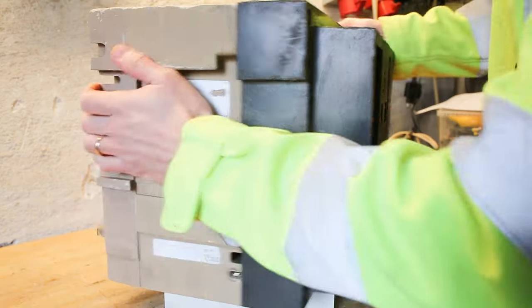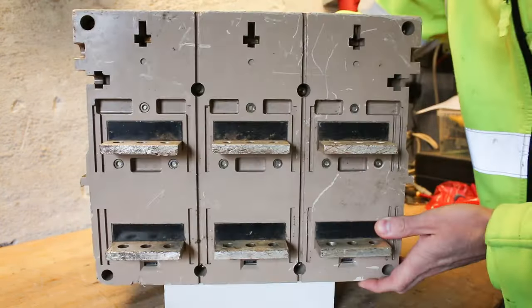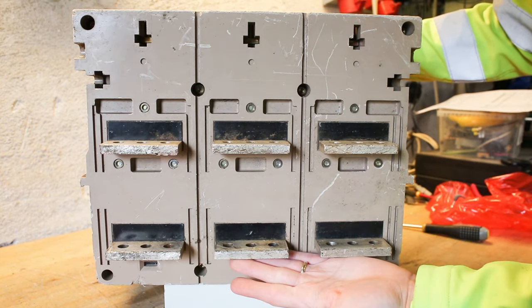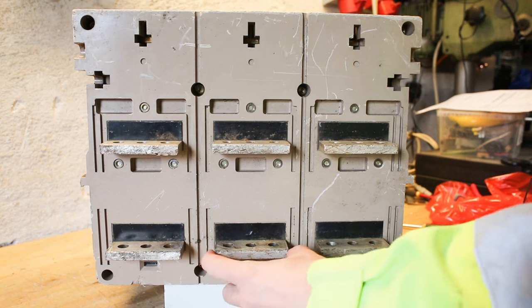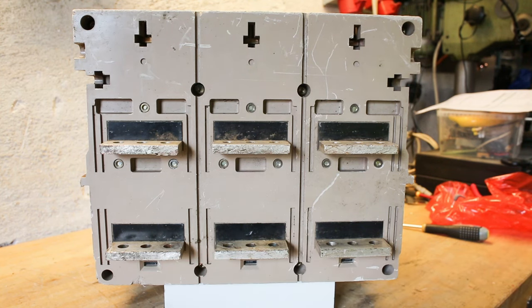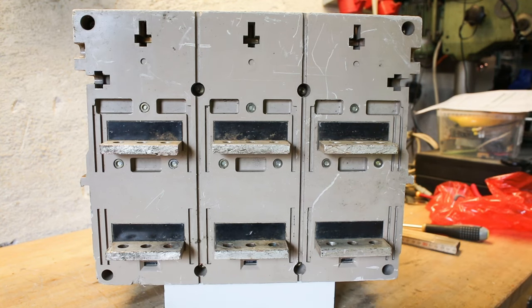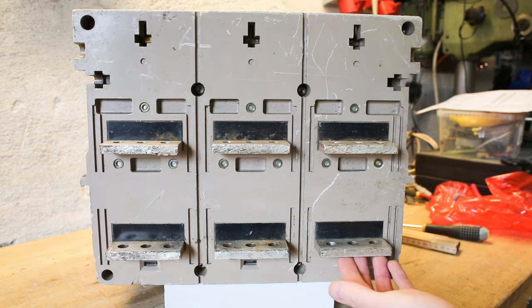Something rated for 1600 amps also has to have some pretty huge terminals. What we have here is something like 8 centimeters by 1 centimeter — so 800 square millimeter thick copper terminals here at the back. Three of them as it's a three-phase unit.